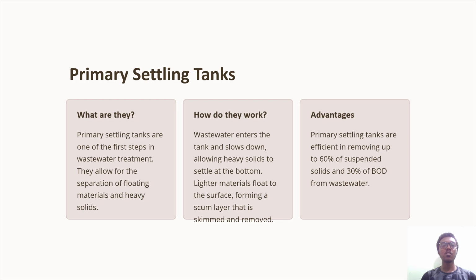The advantages of the primary settling tanks: they are efficient in removing up to 60% of suspended solids and 30% of BOD from wastewater.